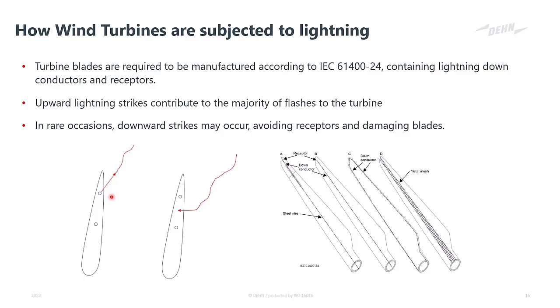So that receptor needs to be rated to a specific charge content, and if it sees more than an accumulated amount, that's when high amounts of damage occur, and that's what we'll focus on. There is, however, a very small chance that you have a downward strike onto a wind turbine. The standard does mention that it's possible, but there's nothing that they can do about it. Because of the way the lightning is formed and strikes, it can strike in between receptors and still damage the blade. There's nothing that you can do to avoid that.